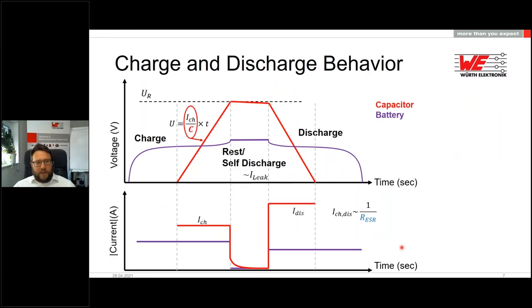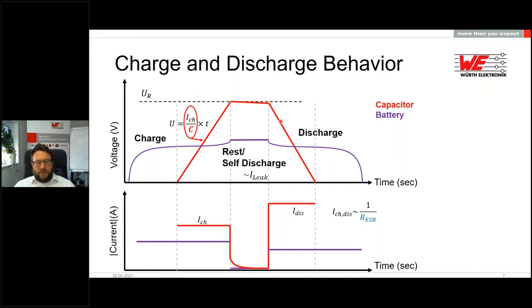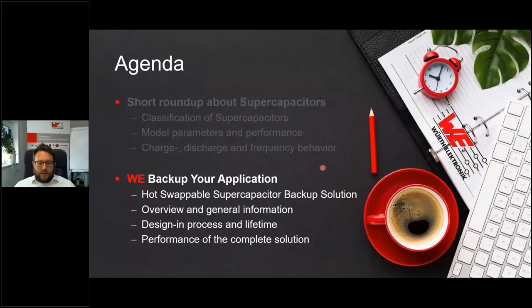When comparing charge and discharge behavior of supercapacitors with batteries, the charge and discharge current for EDLCs is much higher. Charging via constant current produces a linear voltage rise. When discharge starts, there is an initial voltage drop due to ESR, then the voltage falls further linearly — because supercapacitors are still capacitors. In comparison, batteries maintain an almost constant cell voltage at constant current operation.